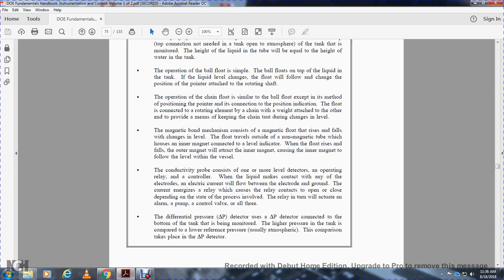The conductivity probe consists of one or more level detectors, an operating relay and a controller. Where the liquid makes contact with any of the electrodes, electrical current will flow between the electrode and ground. Thus, the current energizes the relay, and the relay contacts open or close depending on the state of the process involved. The relay will actuate the alarm, pump and control valve or all three.